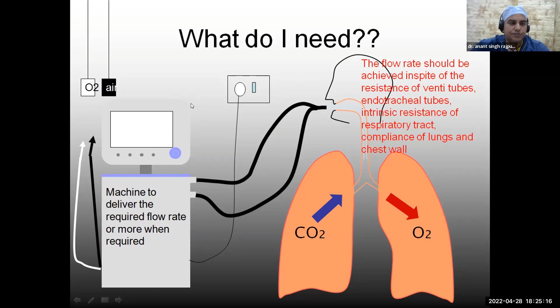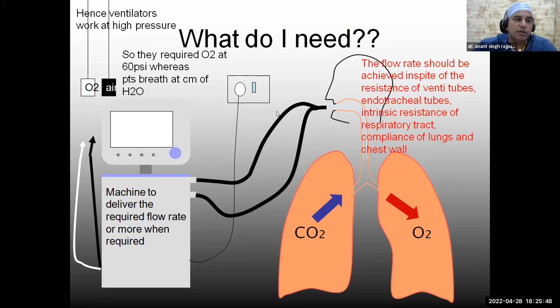ICU ventilators work at higher pressure, and they require 60 psi, whether oxygen or air, whatever we are using, to work. And this pressure difference is required because you want to achieve that flow from this end of the machine to this, that is the patient's lungs, right? So it has to overcome the resistance from the tubings, ventilator tubings, the endotracheal tube, the airways of the patient, the lungs, the chest wall of the patient. All these resistances have to be overcome and the tidal volume has to be delivered, right? So that is why ICU ventilators work on high pressure, right?